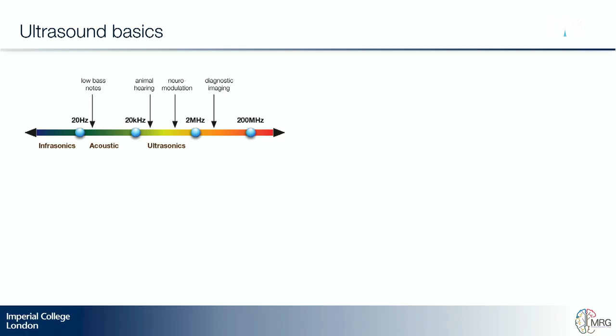Diagnostic imaging, which has obviously been around for a long time with ultrasound, uses really high frequencies in the several megahertz range, because at those frequencies you get very high spatial precision of the ultrasound beam. Neuromodulatory techniques use slightly lower frequencies, around 250 kilohertz to about 2 megahertz, because these frequencies are better able to pass through the brain, through the skull.